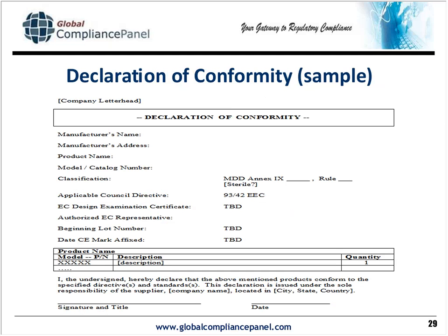Whoever you're using as a notified body, work with them to come up with the format they prefer to use, because they're the ones that are going to be auditing you and defining it. And generally, in difference from the FDA, you're paying your notified body. They've got two arms. They've got the arm that helps you comply, and then they've got the arm that audits you. Well, the arm that helps you comply, that's what you're paying them to do, to help you to meet the requirements to get the CE mark on your product to sell it in Europe and some other countries that accept the CE mark. So again, you're working with them as a partner.